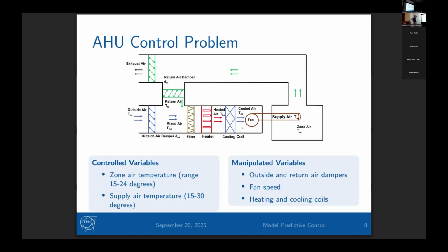For HVAC, where you have air handling units, this is a typical multivariable control problem, not really a regulation problem—it's about keeping temperatures and maybe humidities within a certain range using a lot of actuators, such as a variable speed-driven fan, cooling and heating coils, and dampers to control airflow. You're interested in keeping things within ranges rather than at a specific set point.